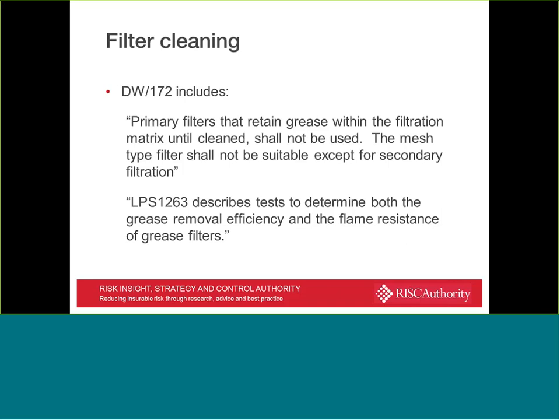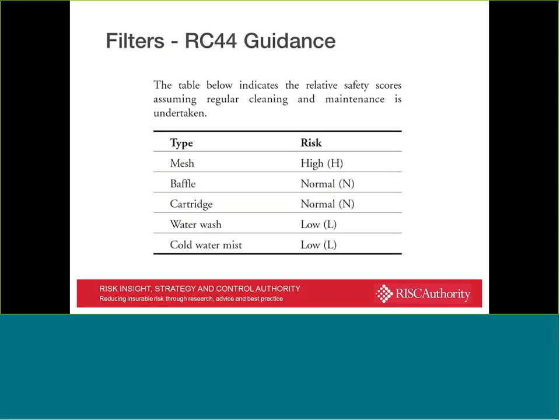But certainly in terms of filter cleaning, I made reference to DW172 earlier, and it's interesting that it states there primary filters that retain grease within the filtration matrix until clean shall not be used. So certainly an encouragement to move away from the use of the mesh type filters themselves because of the potential for significant build-ups. There is a loss prevention standard produced by BRE certification or LPCB, which describes the test to determine both the grease removal efficiency and the flame resistance of grease filters, LPS 1263, and clearly using those types of filters is going to present a far safer environment. Again, referring back to RC 44, there's a little table in there which just summarises what we were discussing, the fact that different types of filter present different types of risk, mesh being the highest, and the water wash or the cold water mist being the lower risk end.